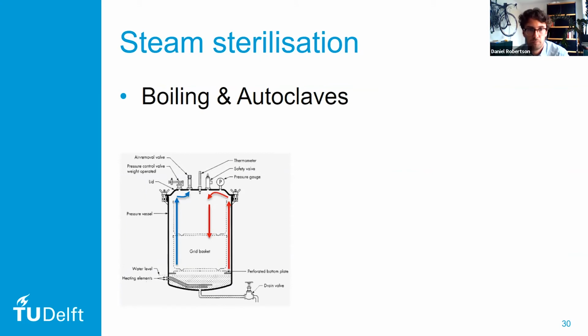And this is when we started to use pressure cookers to sterilize the instruments. Now, these pressure cookers have been developed, and one of the common autoclaves that we see are gravity-based. These generally work by having a water reservoir on the bottom, and this water reservoir will be brought to the boil. This can either be done electrically or even on a stove. The steam will start to rise, and from the top of the autoclave, the steam will start slowly moving down through the autoclave, and it will push out any remaining air.